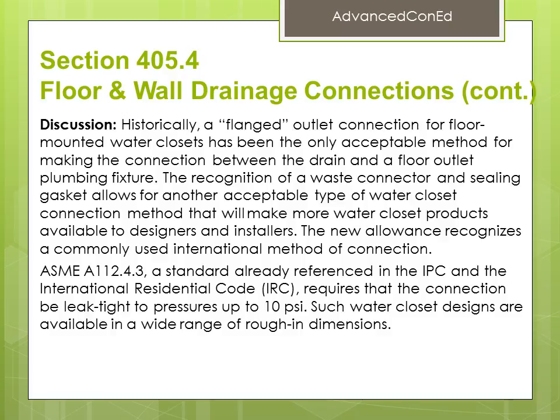ASME A112.4.3, a standard already referenced in the IPC and the International Residential Code, requires that the connection be leak tight to a pressure up to 10 psi. Such water closet designs are available in a wide range of rough-in dimensions.